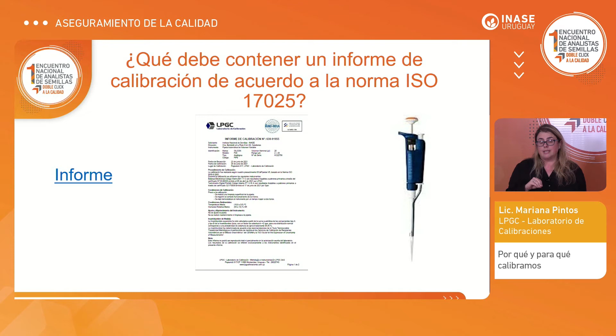The definition is that it's a property of a measurement result whereby the result can be related to a reference through a non-interrupted and documented chain of calibrations, each of which contributes to the measurement uncertainty. In this definition, the reference can be the definition of a measurement unit through its practical realization, or a procedure of measurement, or a measurement standard. This is all the chain we have to follow to reach the pattern that is the reference.